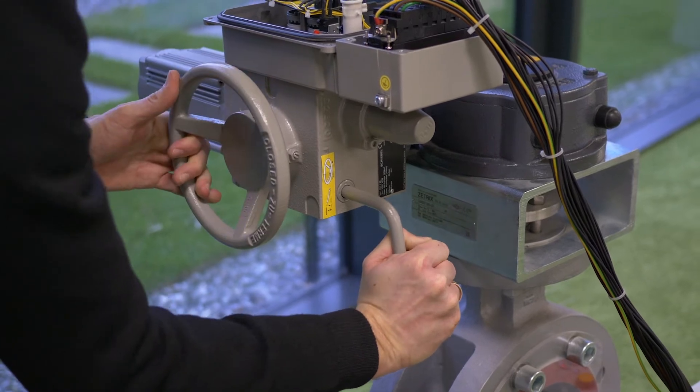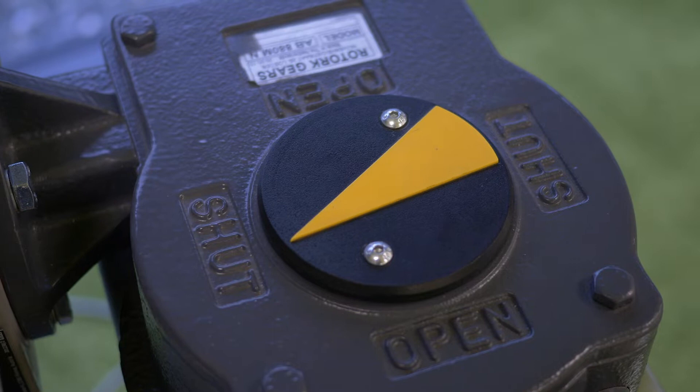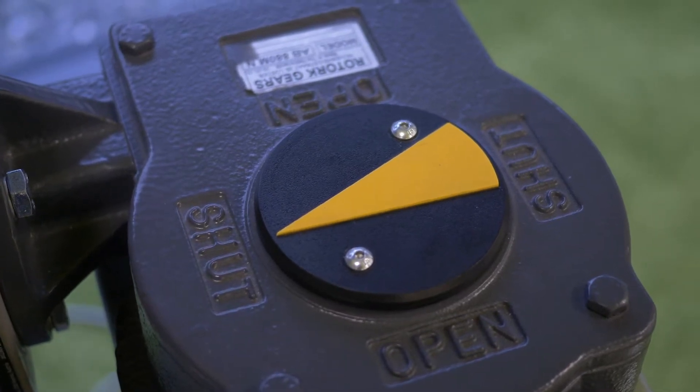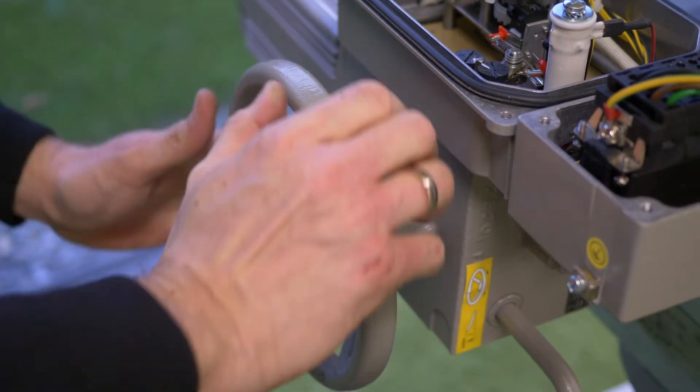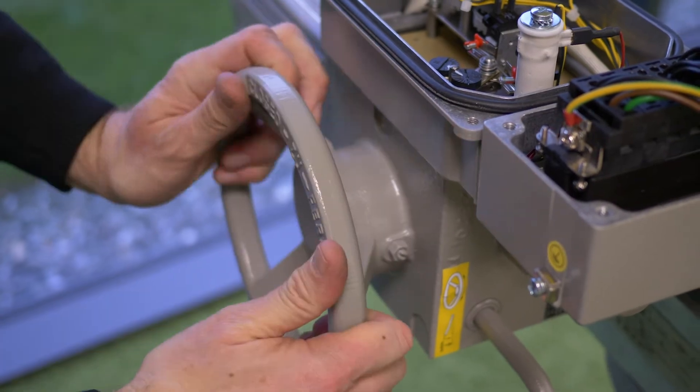Engage the manual override and turn the actuator to close position. After reaching close mechanical end stop, rotate hand wheel half turn back.